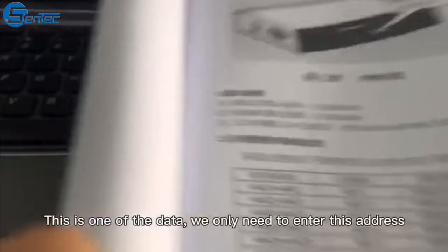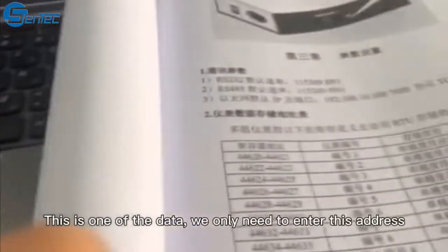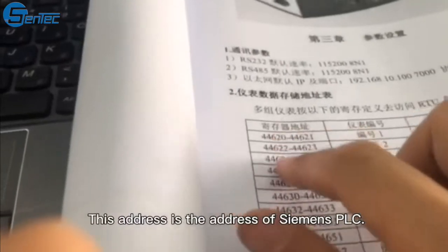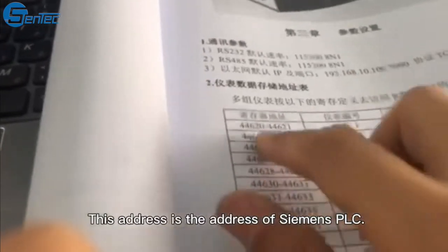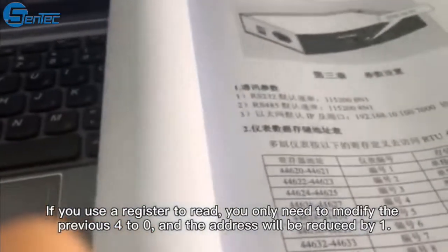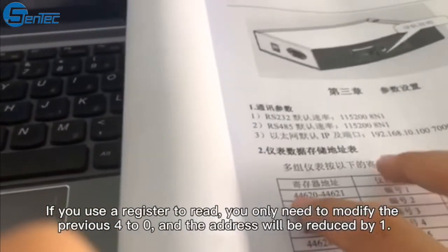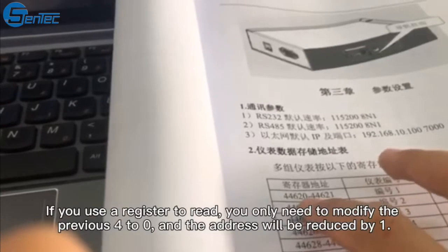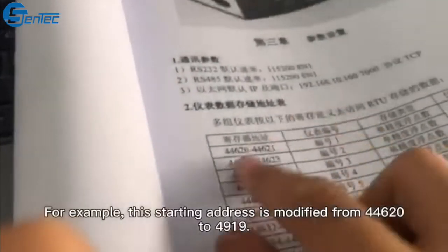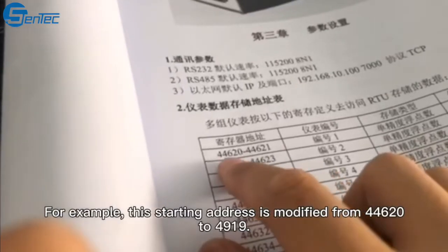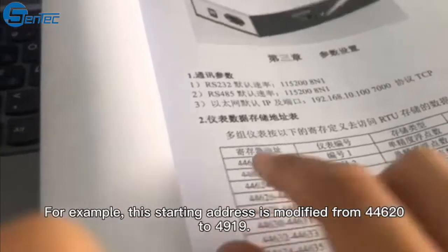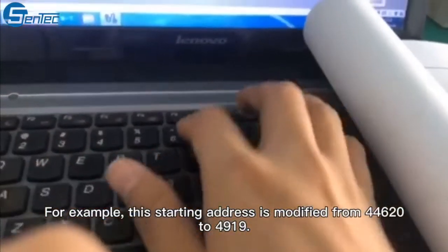This is one of the data. We only need to enter this address. This address is the address used for Siemens PLC. If you use a register to read, you only need to remove the leading 4 and the address will be reduced by 1. For example, this starting address is modified from 44620 to 4619.